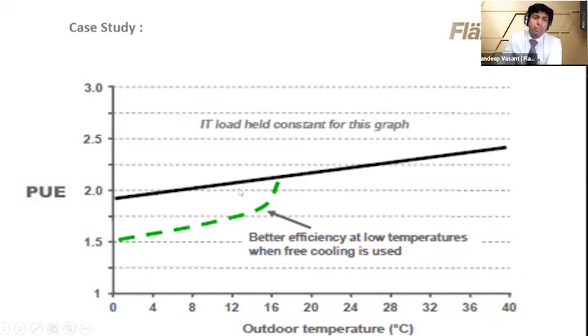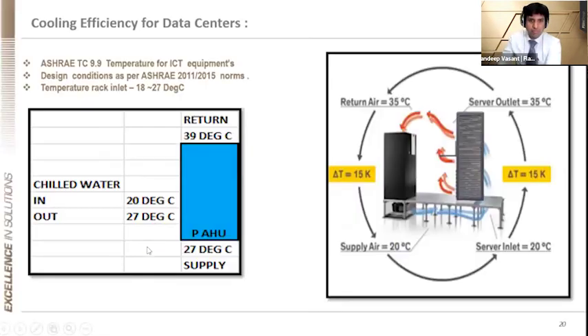We spoke on the PUE as we started the discussion. What happens with free cooling? Obviously the COP would increase, thereby the 30 plus 8, 38% would come down, and thereby PUE would also come down. Again, depending upon the site and application, the unit can be selected, and we could arrive at the exact COP and PUE numbers. Now, as we spoke on the ASHRAE 2011 and 15 document, which says clearly 27 is the supply air, thereby return with 10 or 12.